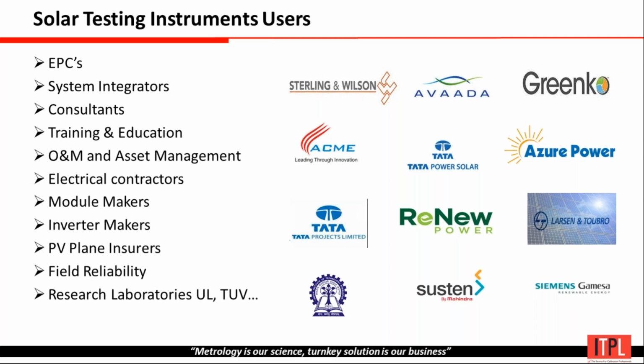For example, you will never have something like 1,000 watt per meter square solar radiation, at which the typical IV curve is provided by the supplier. So on one side we have a standard IV curve provided by the supplier, and at the same time if we have an actual IV curve tested under varying solar radiation, maybe measured at 700 watt or 650 watt or whatever best possible conditions, these two will not match.